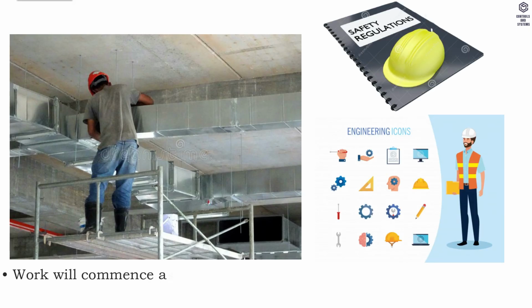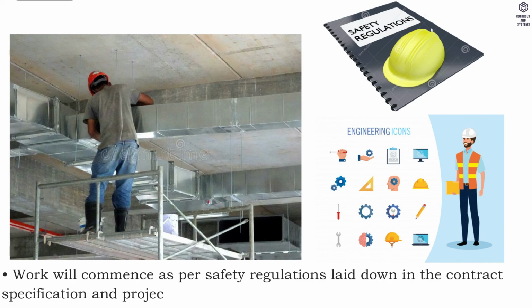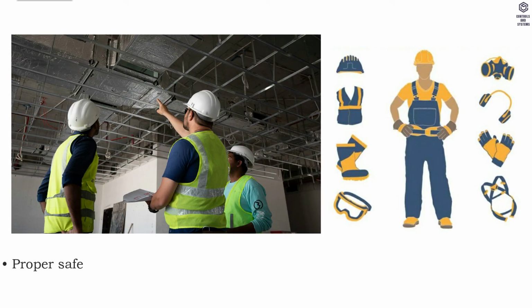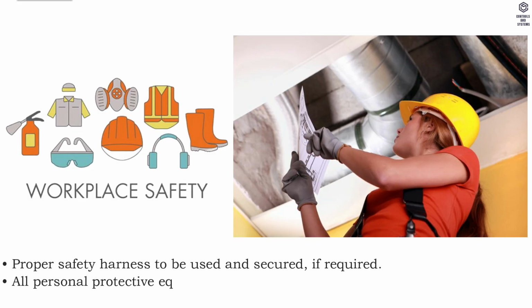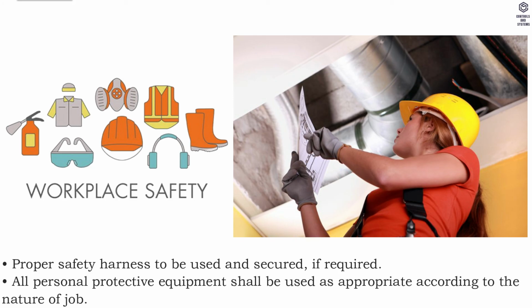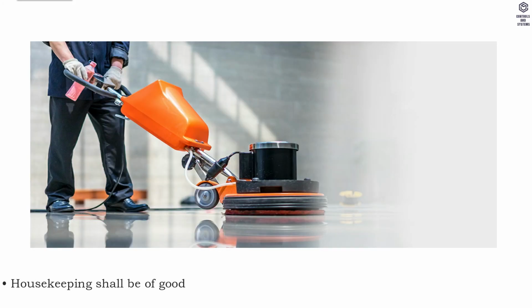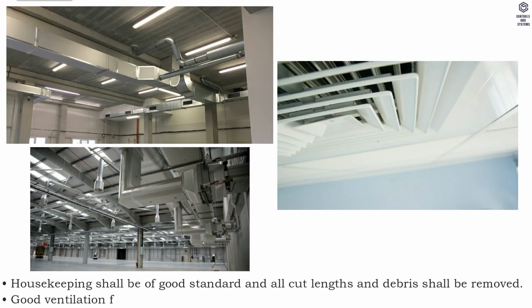Safety. Work will commence as per safety regulations laid down in the contract specification and project safety plan. Proper safety harness to be used and secured, if required. All personal protective equipment shall be used as appropriate according to the nature of job. Housekeeping shall be of good standard and all cut lengths and debris shall be removed. Good ventilation for ductwork insulation shall be ensured.